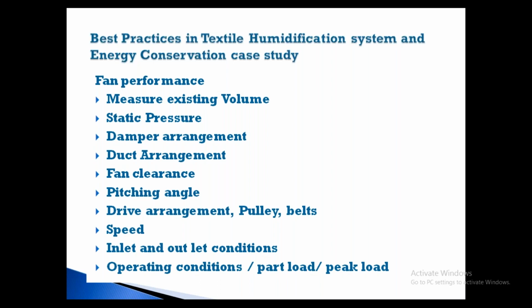So your efficiency is based on that, as well as the bell mouth from the supply side and from the outlet side also. When you have a cone for the air movement, for the path, the bell mouth cone is fixed on the supply side of the fan. It will improve the flow of the air, it will improve performance also, and that is a saving of power. Definitely there is a good saving of power.